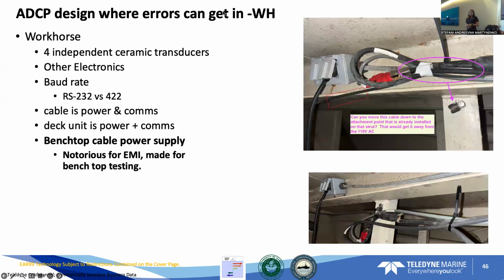Our bench top cable is very notorious for having a lot of EMI and electrical interference. So when installing, whether it's bench top or any cable, just be very careful. This is an example of a situation where they had a little bit of electrical interference based on where it was mounted, and just shifting that cable down so it's not attached to that other power supply got rid of it. So be really careful when installing the cable that you're securing it in a place where it's not going to have any interference with any other power sources.